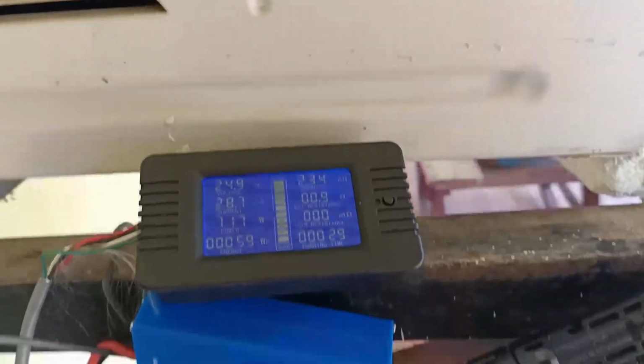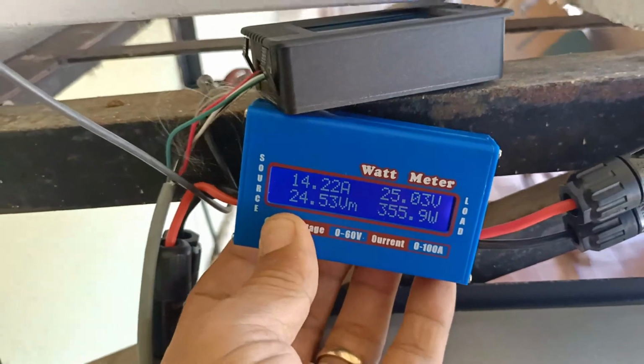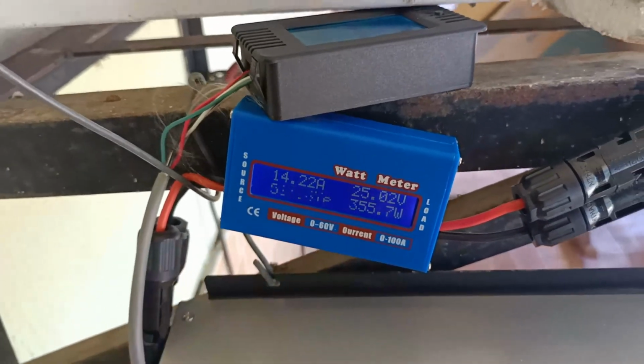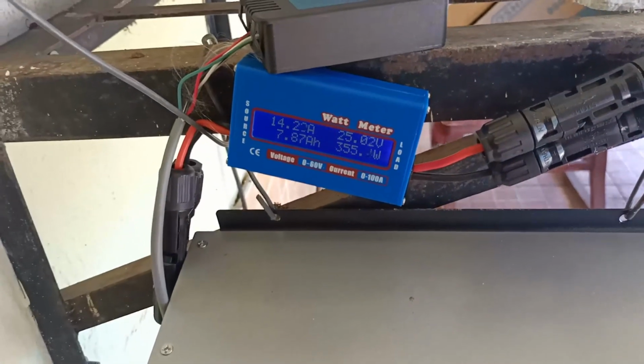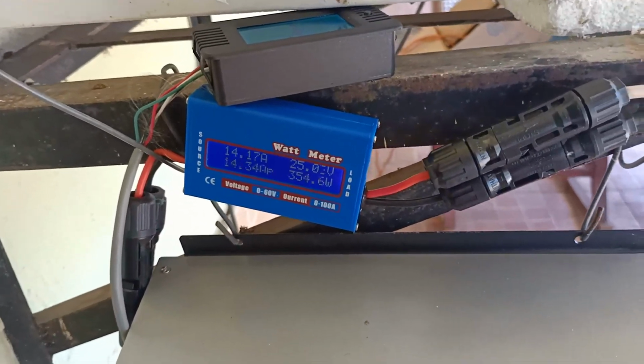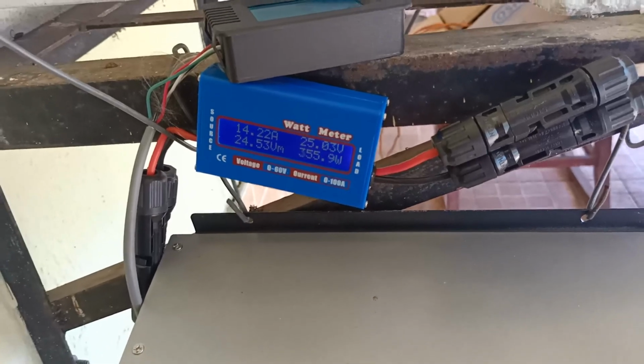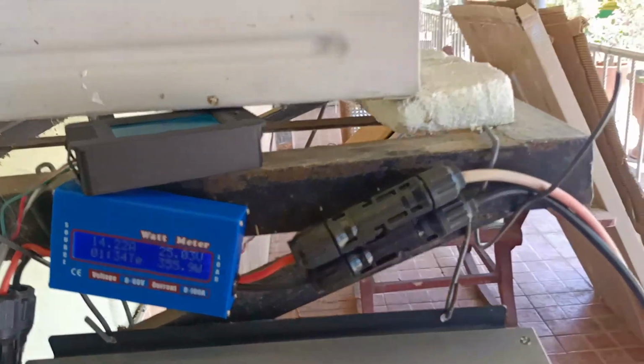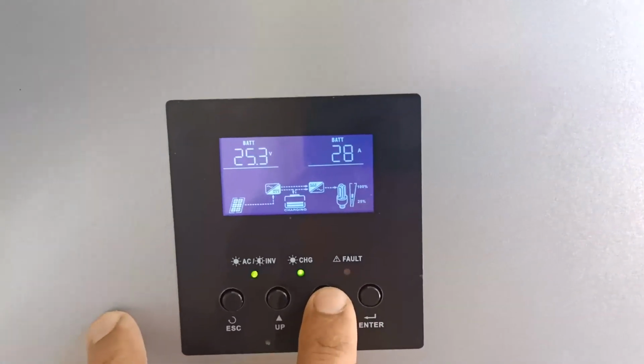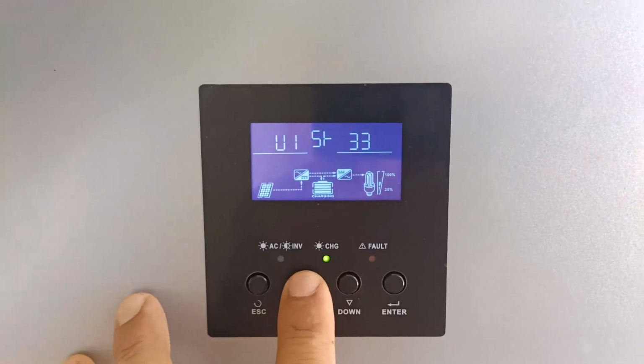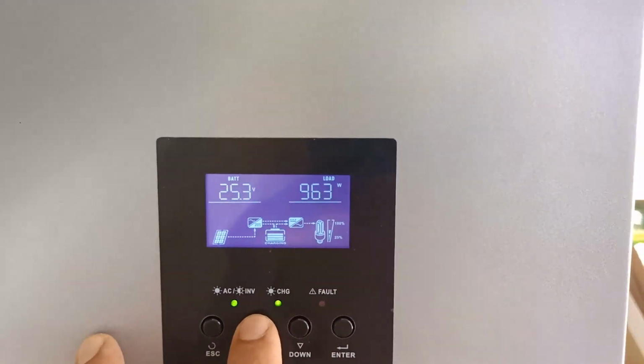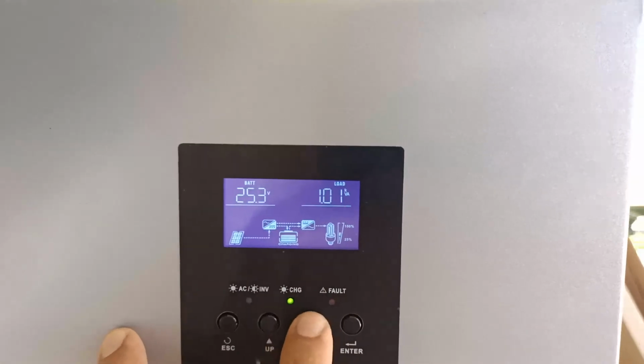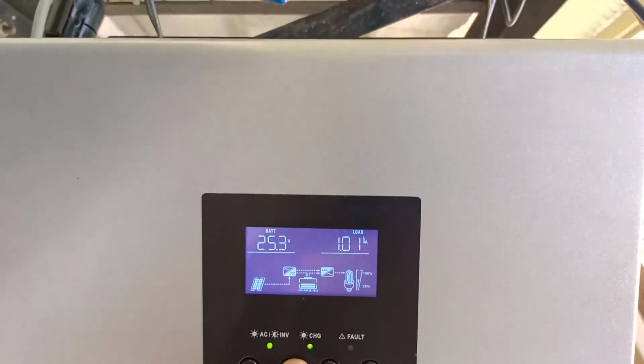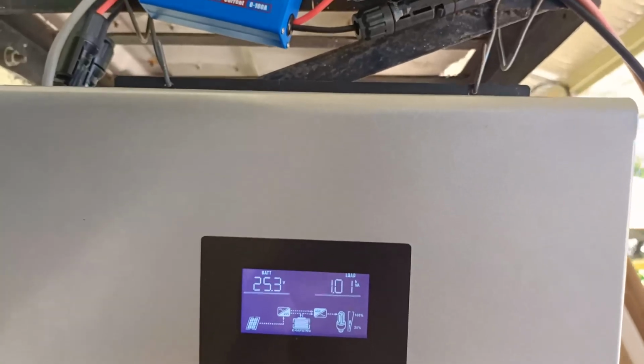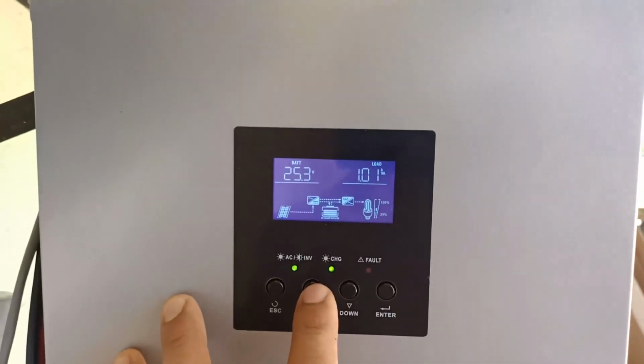So coming out of the battery is 28 amps, and the share load of the solar is 14. So 28 plus 14 is 40-something amps. It's actually a lot, 42 amps. And it's because it's now running at 1 kilowatt or 1 kVA. That's why. So if I remove the solar, then we would see what 1 kVA looks like.